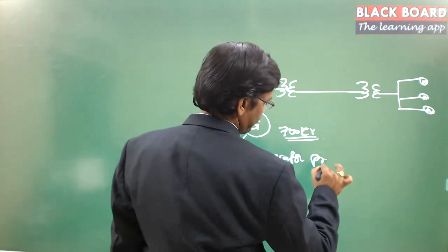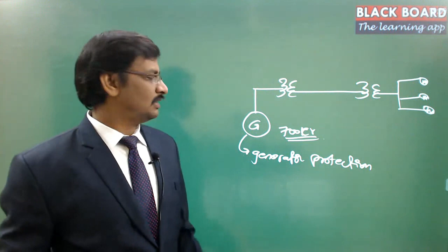For generator protection techniques, we have to be aware what kind of problems can occur in the case of the generator. Suppose because of some reason the two phases got short circuited. The reason can be anything - suppose the rotor gets spoiled and is trying to thrash out, and these two wires are joined. Then there is a huge amount of circulating current that is going to be generated. That circulating current will provide a huge amount of heat.